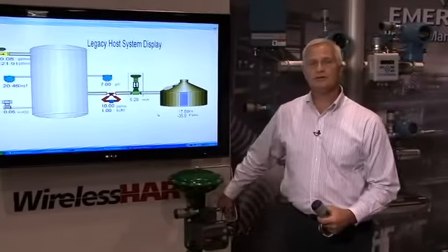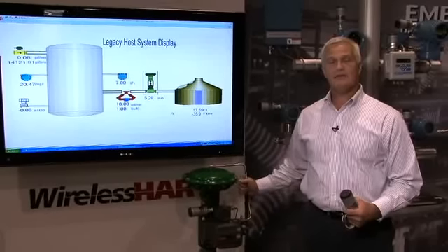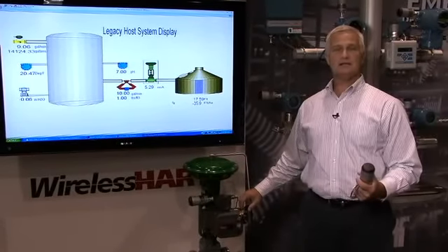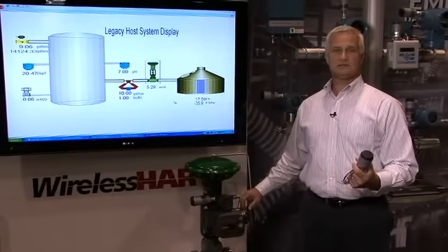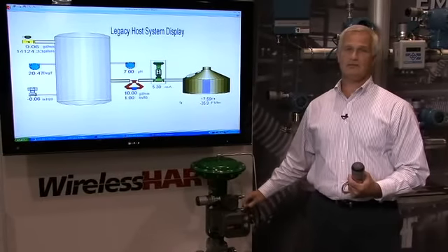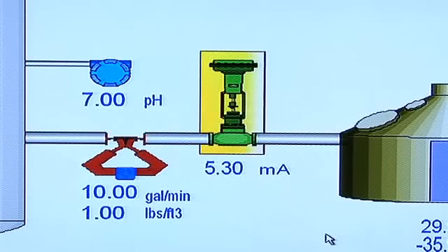The third thing that I want to show you is, how many of you have, in the past, had an issue with a control valve and not realized it until the process is completely upset. In this case, what we did was we pulled the air off the valve and released the signal.